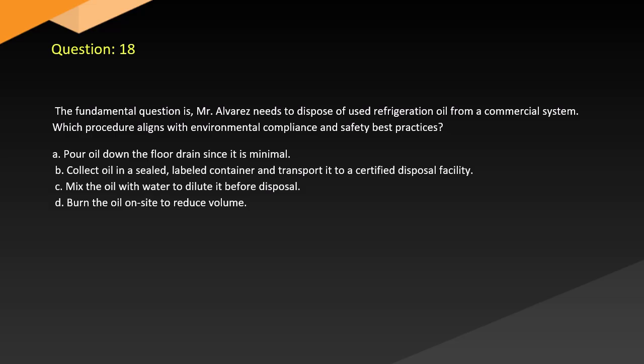Question 18. Mr. Alvarez needs to dispose of used refrigeration oil from a commercial system. Which procedure aligns with environmental compliance and safety best practices? A. Pour oil down the floor drain since it is minimal. B. Collect oil in a sealed labeled container and transport it to a certified disposal facility. C. Mix the oil with water to dilute it before disposal. D. Burn the oil on site to reduce volume.